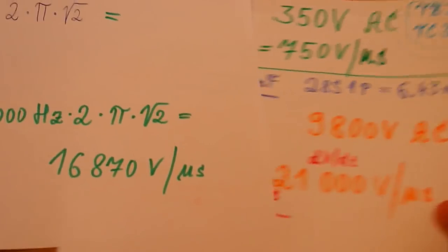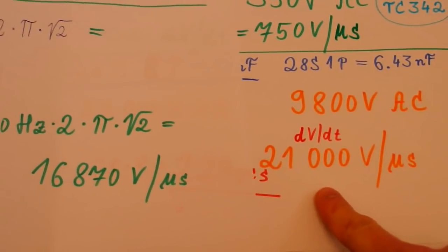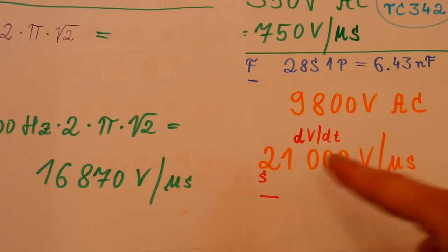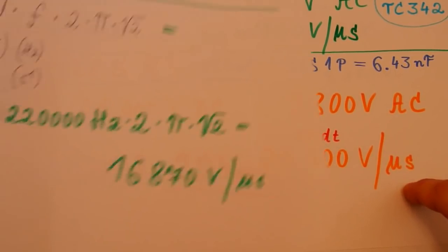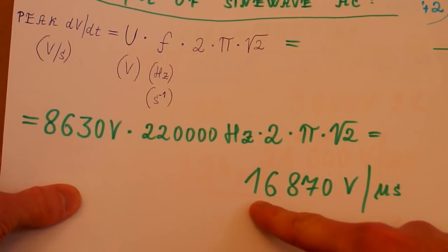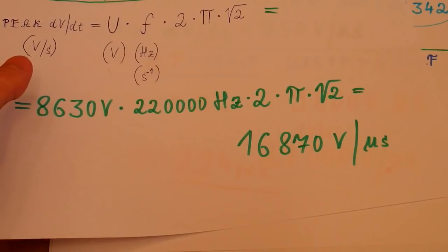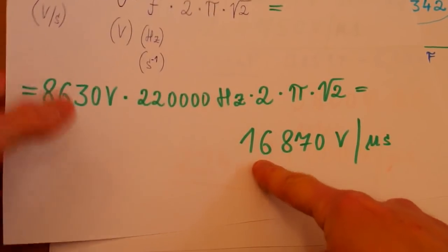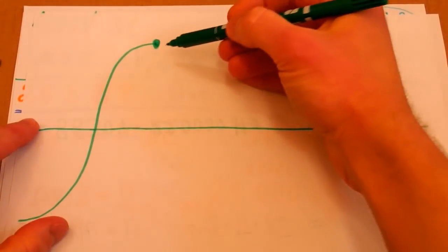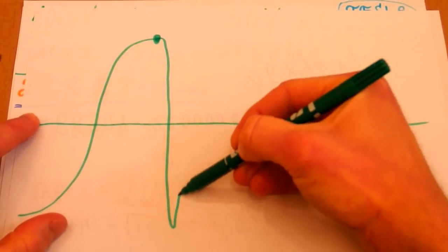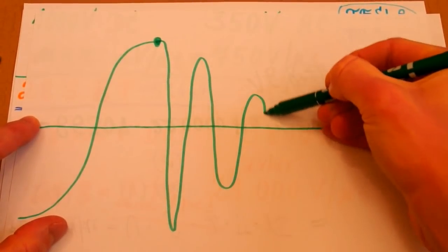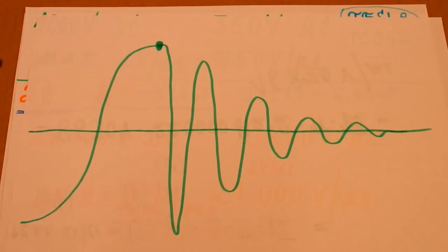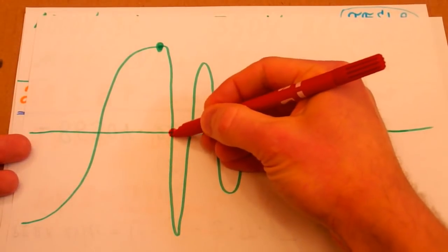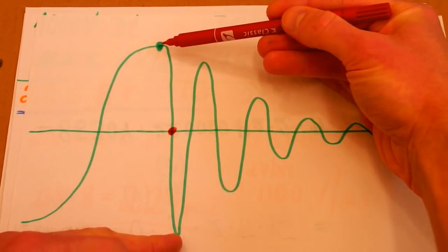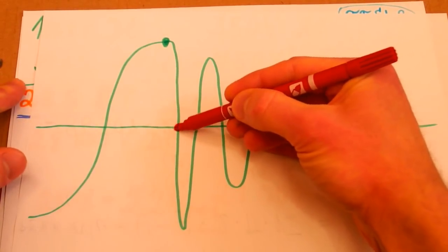So here's the result, and this value is actually lower than the maximum rating of my capacitor bank. So it should be fine. My capacitor bank is rated 21 kilovolts per microsecond, and the actual peak dV/dt is going to be just about 17 kilovolts per microsecond. It's not that much headroom, but this is the worst case maximum peak. The spark gap basically triggers here and you get a high frequency sine wave, which slowly fades out, like this. And this peak dV/dt only happens here, when you have the maximum amplitude, but also you are in the steepest point of a sine wave.